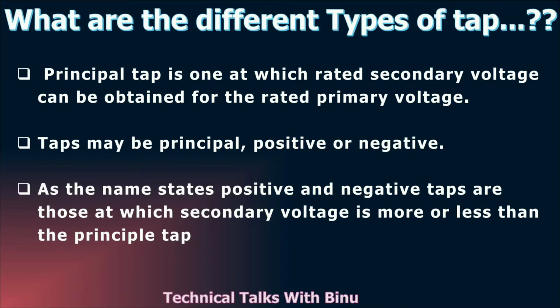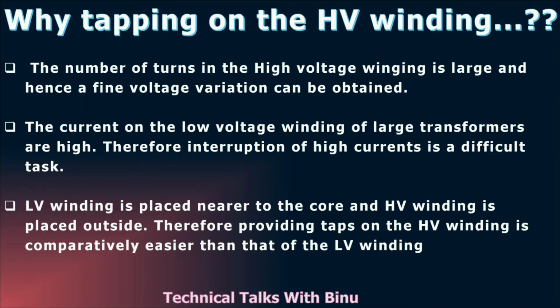As the name states, positive and negative taps are those taps at which secondary voltages are more or less than the principal tap. Normally, the tappings are provided on the HV windings. Now we can discuss why taps are provided on the HV winding. First point is that the number of turns in the HV windings are larger and so fine voltage control can be obtained in the HV winding.